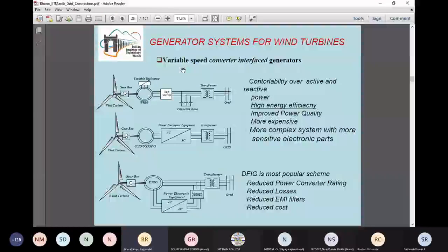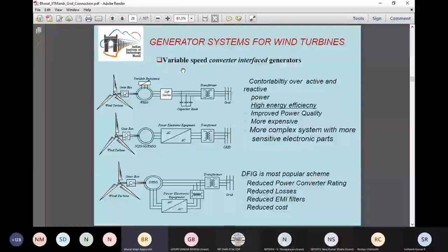That's why, based on this range, the rating of this converter is also almost a third of the stator rating. Hence, as compared to the middle scheme, the rating of the power converter is one third. That's why the overall cost of this scheme is also less. That's why this doubly-fed induction generator based scheme with a back-to-back power converter on the rotor side is the most popular scheme, and the largest number of wind generators installed are based on the doubly-fed induction generator. So this is an important scheme.